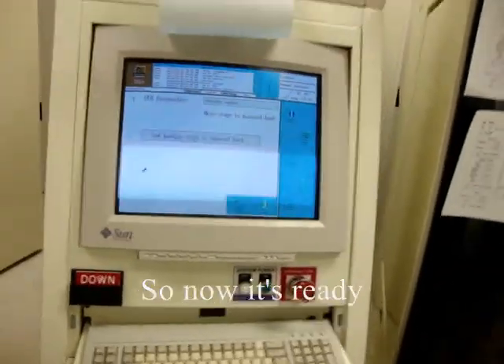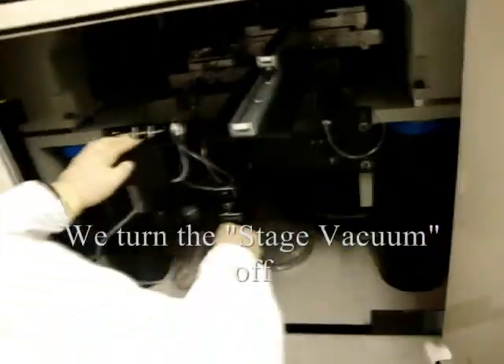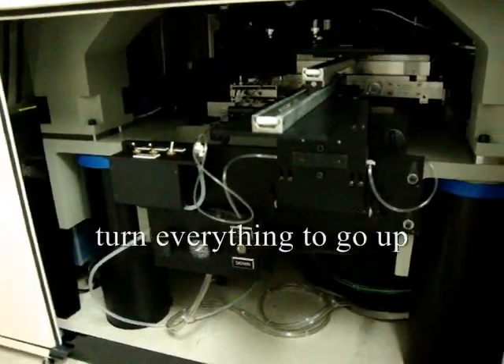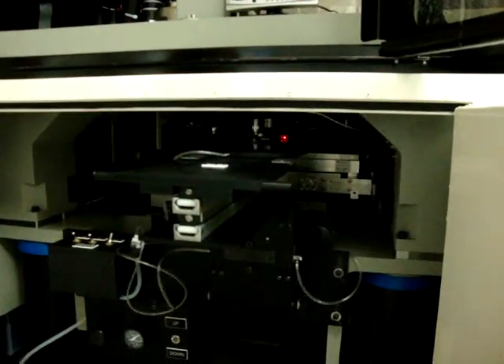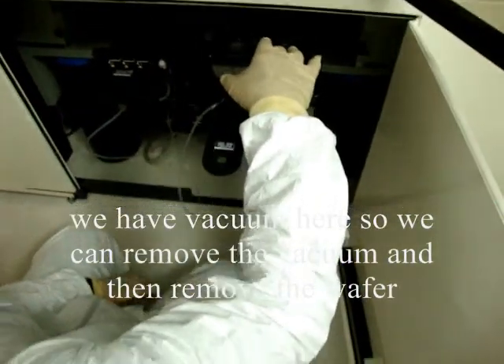Now it's ready — remove the wafer. We have to watch the tubing at all times because it will snag. Push the plate in, and then turn the stage vacuum off. We want everything to go up, and then pull it out. There are two cutouts here so you can grab the handle on the chuck. And there it is — we have vacuum here so we can remove the vacuum to remove the wafer.